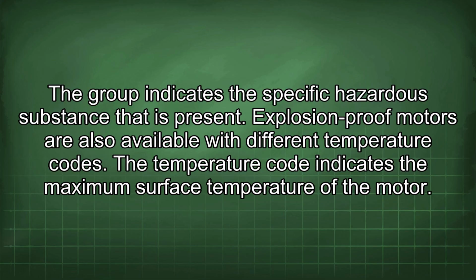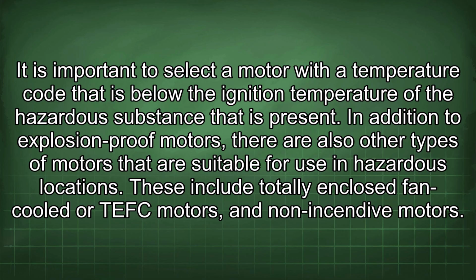Explosion-proof motors are also available with different temperature codes. The temperature code indicates the maximum surface temperature of the motor. It is important to select a motor with a temperature code that is below the ignition temperature of the hazardous substance that is present. In addition to explosion-proof motors, there are also other types of motors that are suitable for use in hazardous locations. These include totally enclosed fan-cooled or TEFC motors and non-incendive motors.